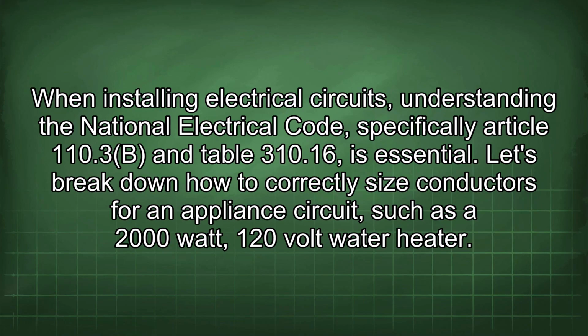When installing electrical circuits, understanding the National Electrical Code, specifically Article 110.3b and Table 310.16, is essential. Let's break down how to correctly size conductors for an appliance circuit, such as a 2000-watt, 120-volt water heater.